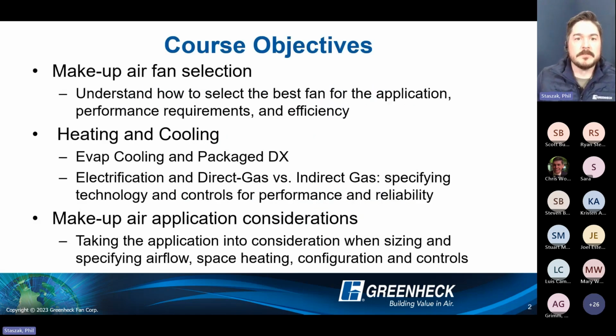So here are the course objectives. The biggest change with makeup air, as far as a technological advance, and one thing we're pretty excited about as a manufacturer, is how we're bringing in outside air. The technology with direct gas, indirect gas, and electric heat has pretty much been there from the get-go. But as for how we bring in that outside air, there's the shift toward direct drive fans, and we'll talk about some of the benefits there.